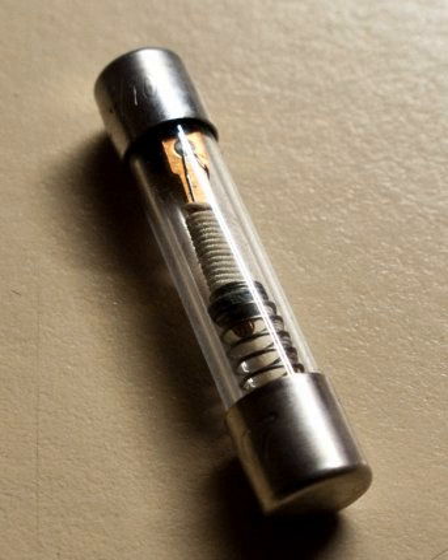Topic: High voltage fuses. Fuses are used on power systems up to 115,000 volts AC. High-voltage fuses are used to protect instrument transformers used for electricity metering, or for small power transformers where the expense of a circuit breaker is not warranted.